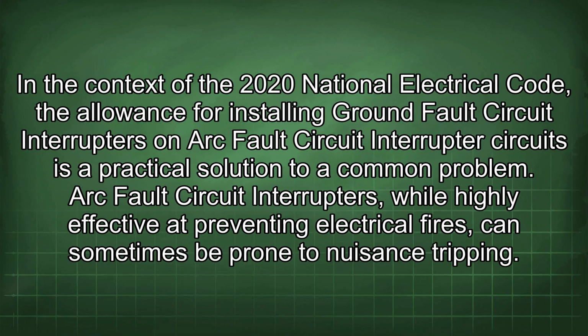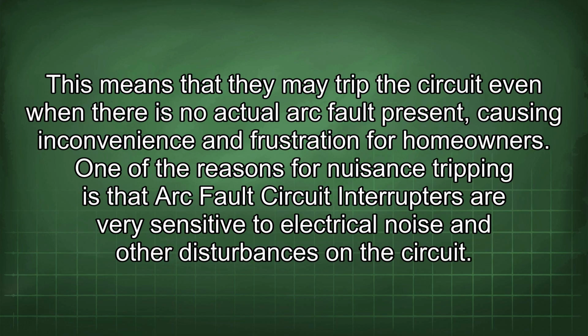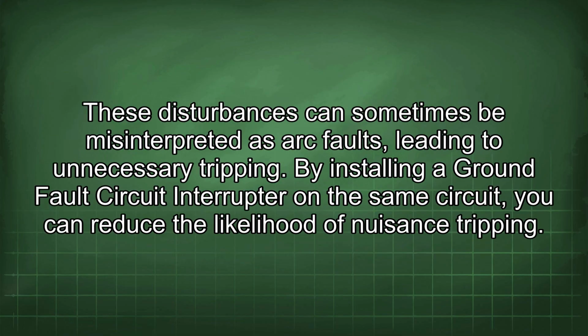In the context of the 2020 National Electrical Code, the allowance for installing ground fault circuit interrupters on arc fault circuit interrupter circuits is a practical solution to a common problem. Arc fault circuit interrupters, while highly effective at preventing electrical fires, can sometimes be prone to nuisance tripping. This means that they may trip the circuit even when there is no actual arc fault present, causing inconvenience and frustration for homeowners. One of the reasons for nuisance tripping is that arc fault circuit interrupters are very sensitive to electrical noise and other disturbances on a circuit. These disturbances can sometimes be misinterpreted as arc faults, leading to unnecessary tripping.